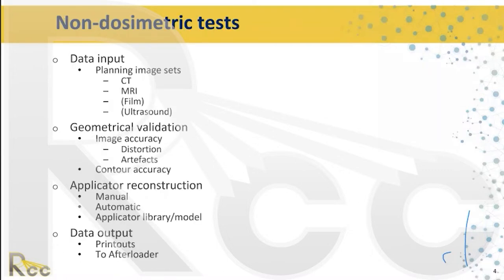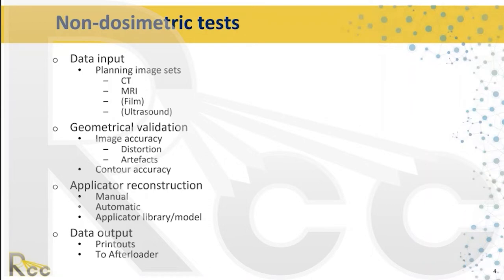For non-dosimetric tests, you have basic data input and output validation. The data input for a typical brachytherapy dose calculation can be either 2D or 3D — it could be film, 2D ultrasound, or 3D CT or MR, and sometimes a fusion between CT and MR. Geometrical validation also has to test image accuracy, especially since brachytherapy applicators can distort both the anatomy and the imaging, as they are not made of natural soft tissue materials.